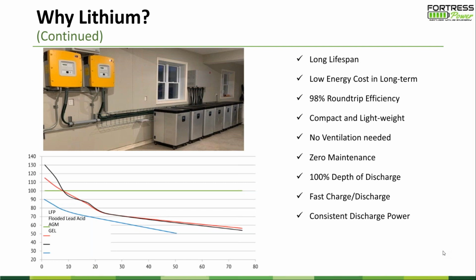A good thing about this lithium is zero maintenance, no ventilation needed. A lot of lead acid, especially flooded lead acid, always need a ventilation system because of the emission from the chemical reaction. And in terms of depth of discharge, lithium can do 100%, lead acid 50% maximum.